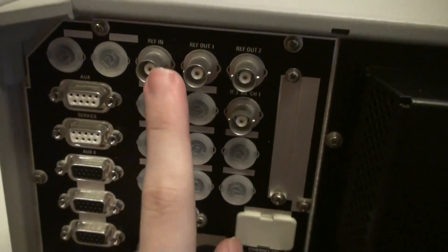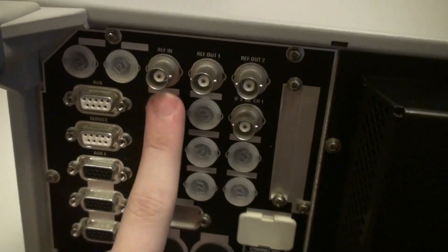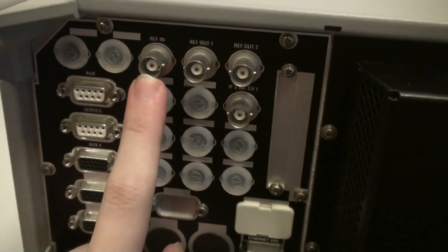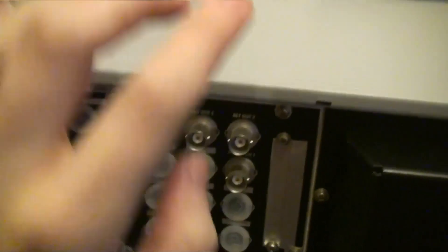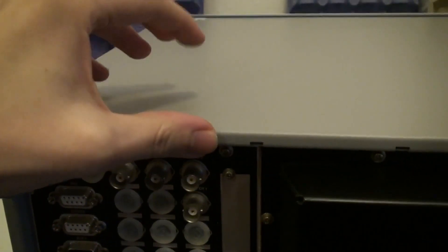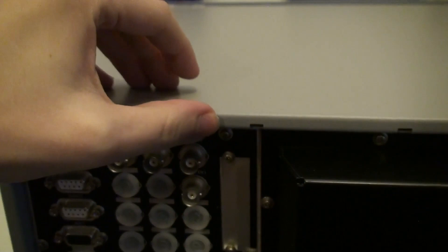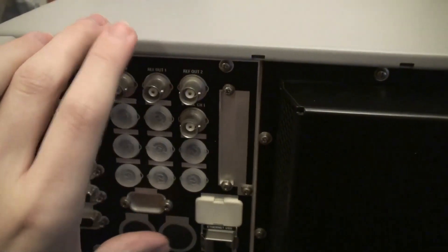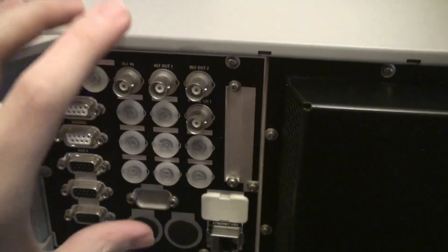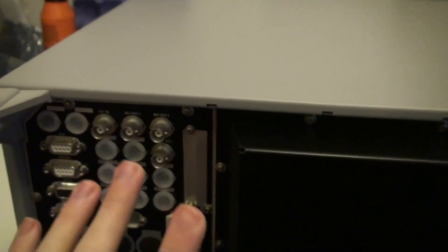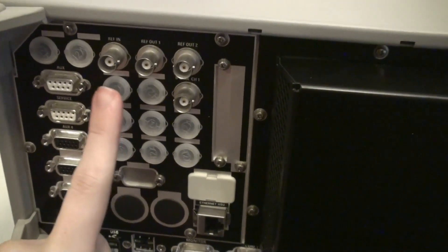And then we have a reference input. In case you have a 10MHz reference lab standard. Now this option, I don't have anything in the lab that's more stable and more likely calibrated than this is. Because internally inside of this we have an ovenized oscillator. We actually have the highest stability option that this unit can come with.